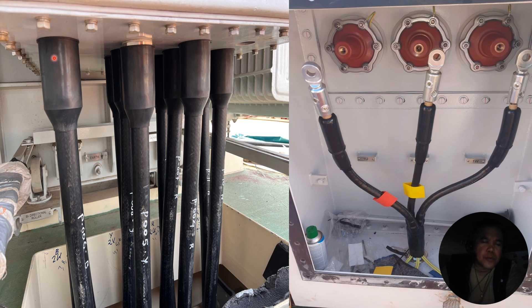Okay, so now as you can see how they run their cable through their compartment. This is a low voltage and this is the high voltage cable. And after that, once you have installed completely, you provide the glanding, cable shroud, and then lugs in this area for our high voltage, and then you provide cable tagging and identifications: red phase, yellow, and blue phase. So everything must be clear, and then earthing is there, and then the gland plate. And the earthing should be clear, everything.